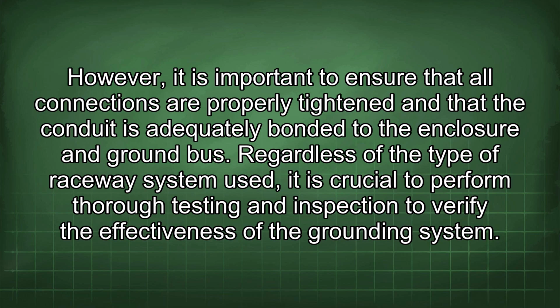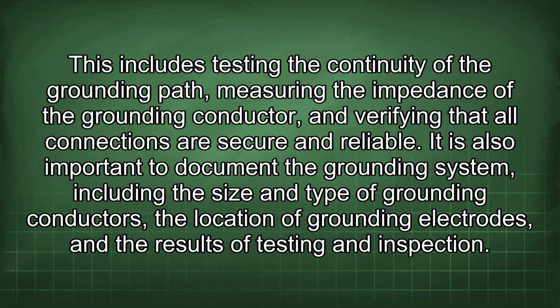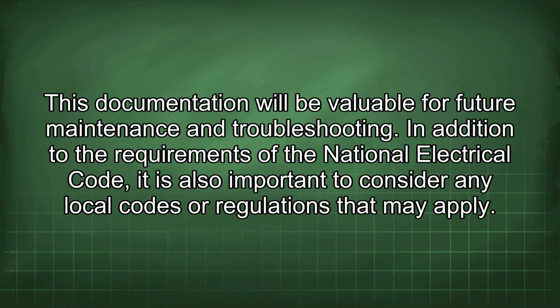Regardless of the type of raceway system used, it is crucial to perform thorough testing and inspection to verify the effectiveness of the grounding system. This includes testing the continuity of the grounding path, measuring the impedance of the grounding conductor, and verifying that all connections are secure and reliable. It is also important to document the grounding system, including the size and type of grounding conductors, the location of grounding electrodes, and the results of testing and inspection. This documentation will be valuable for future maintenance and troubleshooting.